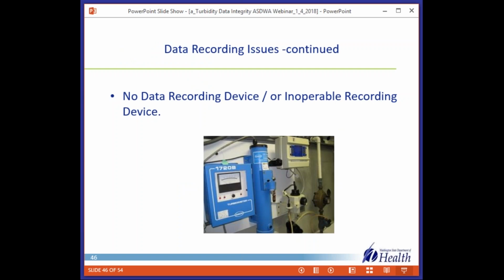Continuing on with recording issues, not just that they don't match, but we had 3 systems where the recording device was broken or inoperable, so it might have just been missing. So that's pretty significant. In this case, data integrity is suspect. The turbidity data reported was based on visual readings of online instruments by the operator during the course of the filter runs. Just a little plug, that is a 1720B, and that was operating a treatment plant up until 2012. So they definitely got their money out of that one.